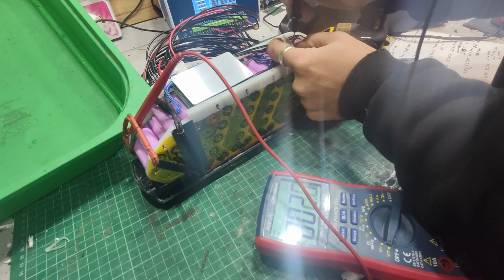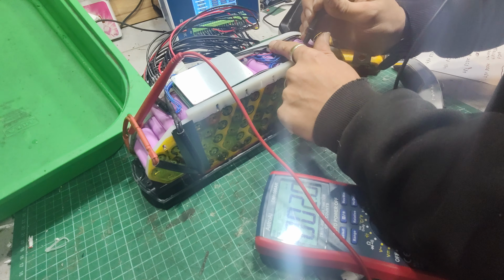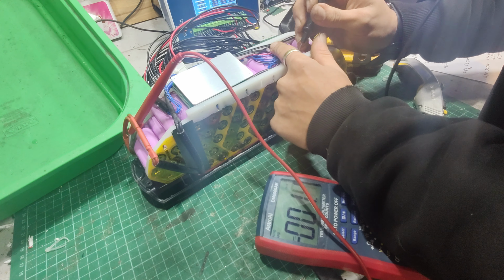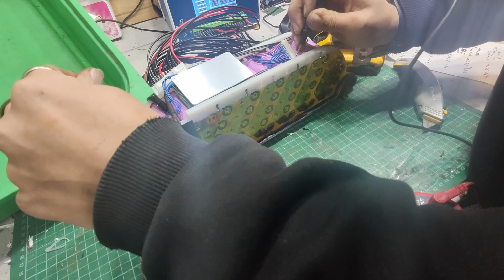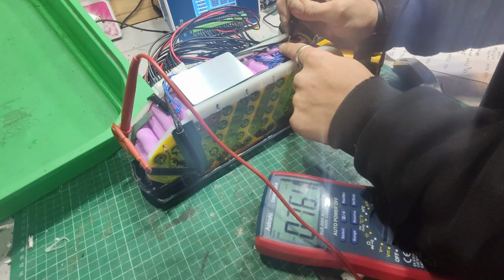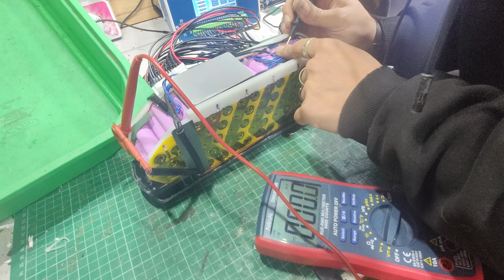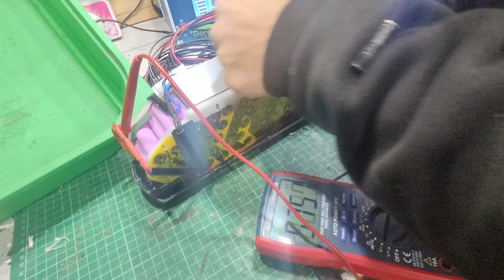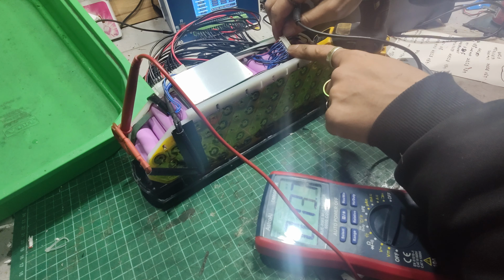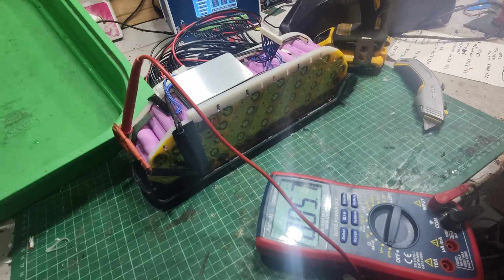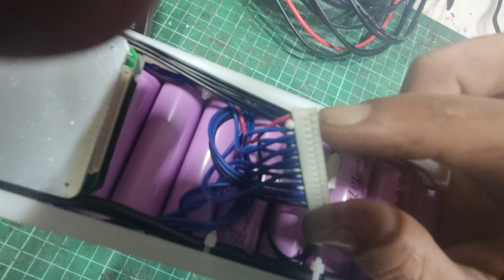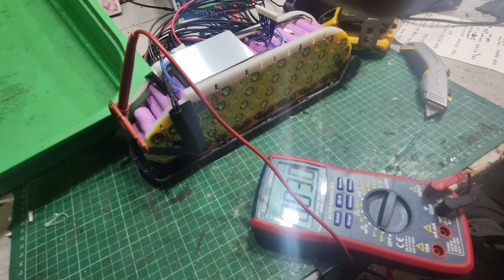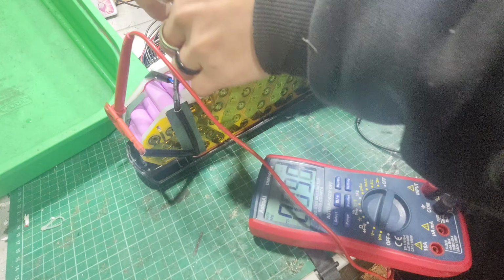See if we can go between - so there's one probe on the positive there, one probe on the negative here on the balance lead. We should get full pack voltage, which I'm not. There it goes, 51.6, and this should be 0, 0. Not. Oh, isn't that weird? They've skipped one in the BMS wiring there - so cell group number 14, there's nothing populated in there, it's actually up here. Bit weird, don't know how much you could see of that, that looked quite poor quality footage. Why would they have done that?